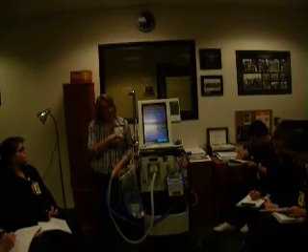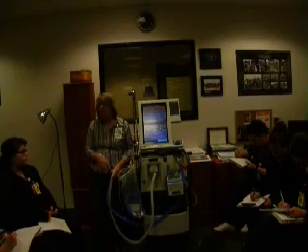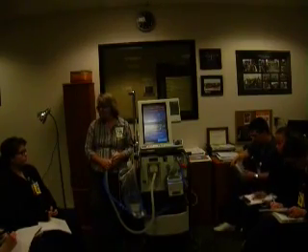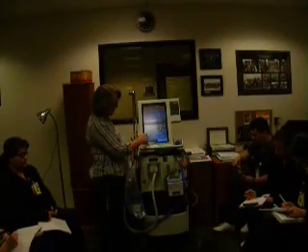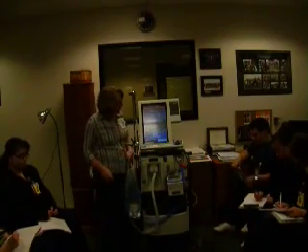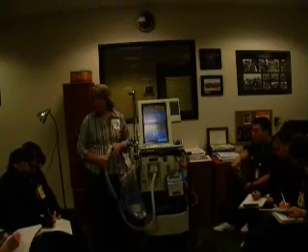So this has no standby, so if you're going to take it off a patient, but you're going to be using it on the same patient when they come back from wherever it is they went, then you just turn it off. When they come back, you use same patient, and it'll have all the same stuff that it had before. But to put it on a new patient, we're going to hit new patient, because that's what we want to do. And then you'll see it has a box for ideal body weight.